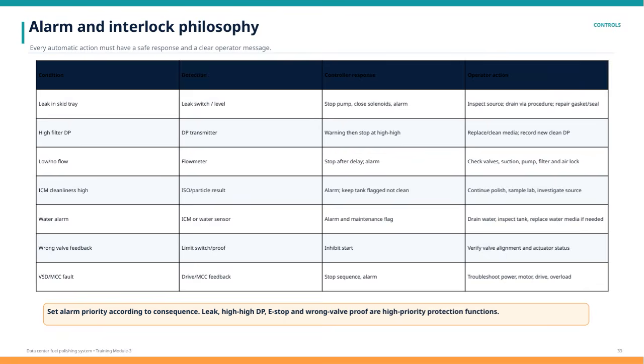Similarly, if there's a high differential pressure across the filter detected by a DP transmitter, the system first issues a warning and then stops at a critical high level. The operator's role here is to replace or clean the filter media and record the new clean differential pressure. Low or no flow situations are managed by stopping the pump after a delay and sounding an alarm, prompting operators to check key components like valves, suction lines, pumps, filters, and air locks.